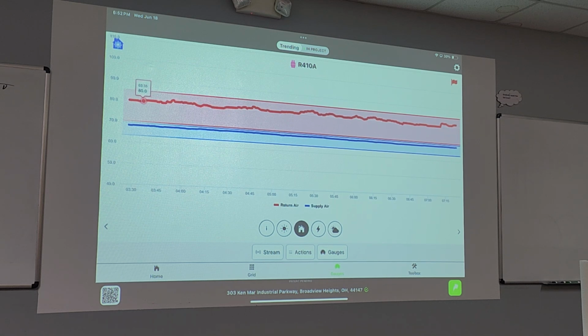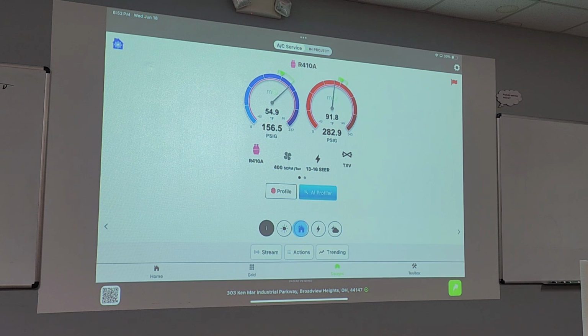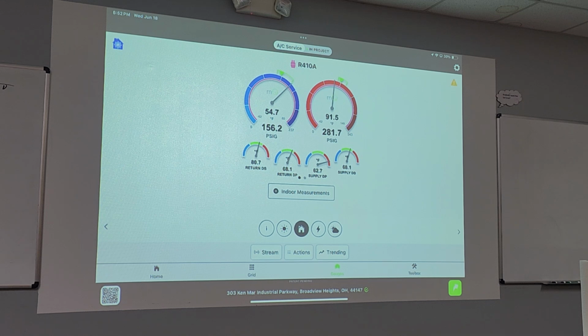So now you have air currents in the duct where you could have a cool spot and a warmer spot. How it calculates the temperature split and your cooling capacity is directly related to what your temperature split is. And depending on where you put your probe, and especially the return probe, that's another one, the return probe is what's screwing with us right now. Return ducts are very weird in that there's not a lot of mix happening in a return. You can put the probe in on one side of the duct, and if there's one return vent that's getting hot attic air or whatever in it, you can have an airstream in the duct where this side of the duct is cool and another side is hot. So you still need to know what the probes are seeing, what the operating conditions are.